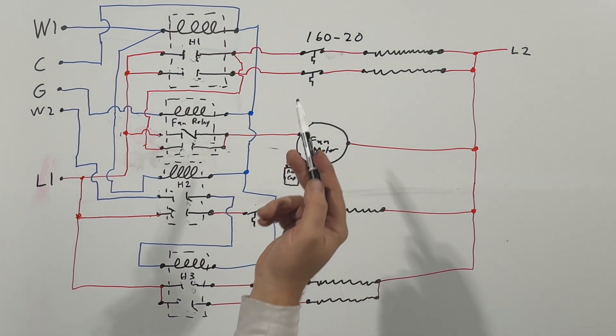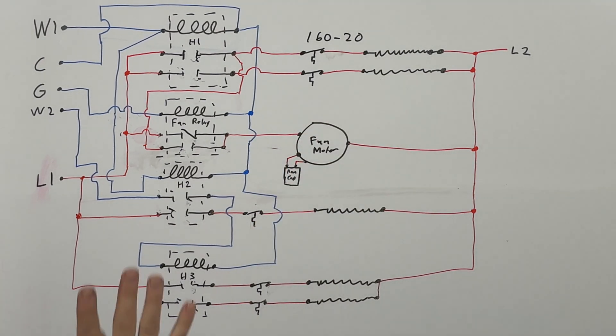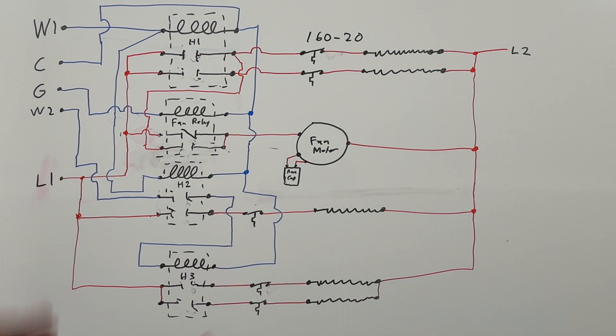And then when they get 20 degrees colder than 160, so that'd be 140, when temperature drops down to 140 they reset and close again. So this is a basic, basic setup of how an electric only heater works.